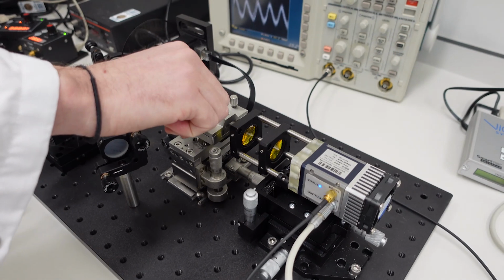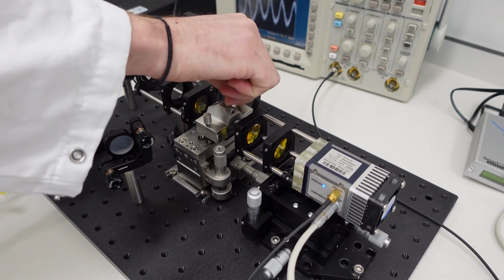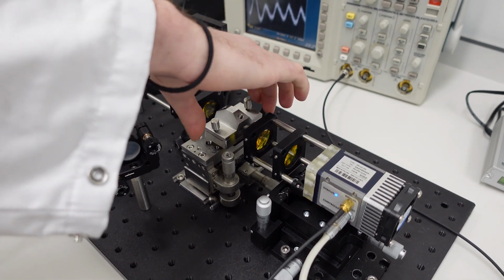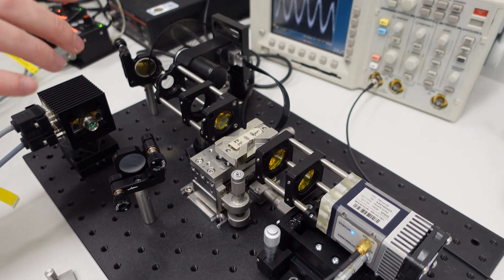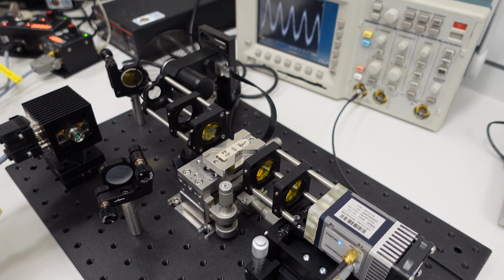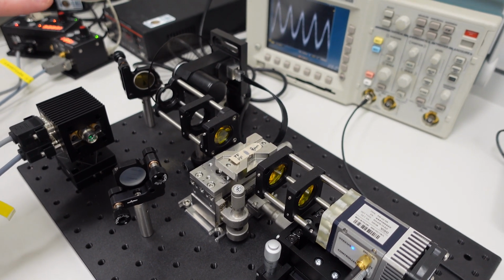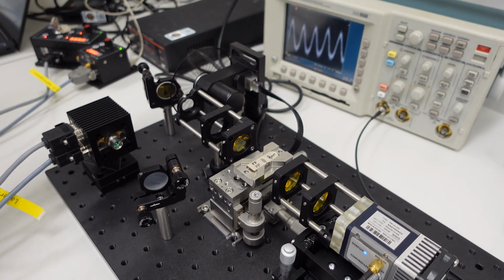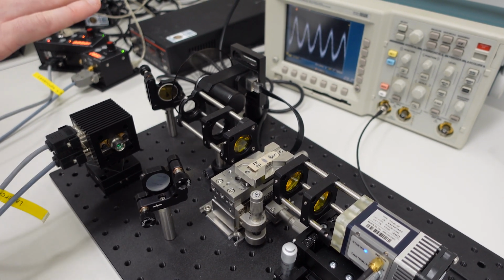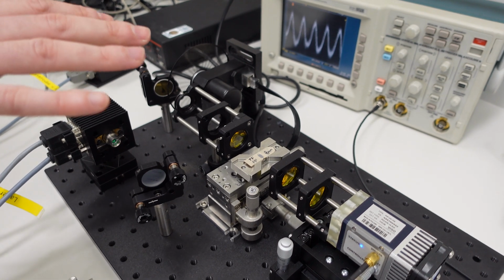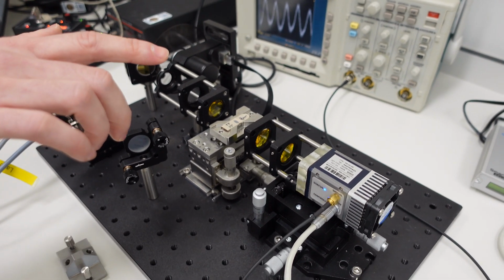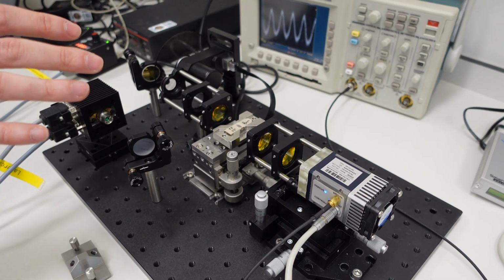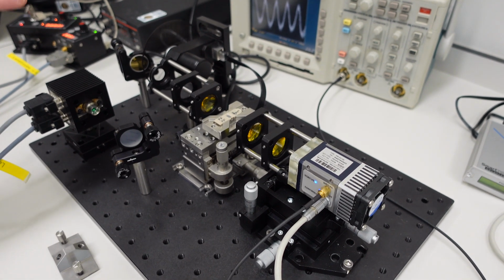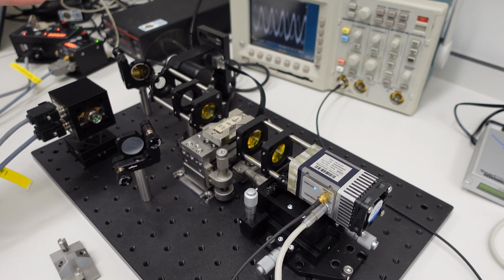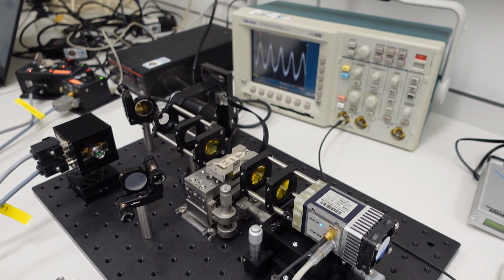The sample is located on the gallium arsenide waveguide, which has a thickness of 6 microns. The samples can be measured in liquid or solid state and will partially absorb the evanescent field produced by the laser light going through the waveguide. Then this difference will be recorded by the detector, which can measure the concentration of different components of our sample.